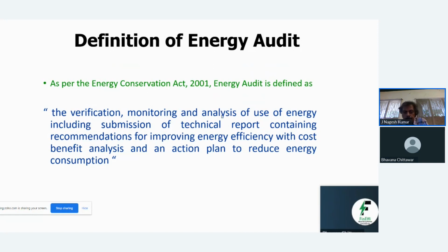If there is a compressor, where do we stop the analysis? We measure the electrical power input to the compressors as part of the energy audit. Diligently, we measure the power using a power analyzer. Today it's becoming a fashion to do the FAD test. I'm not really sure how helpful it is, but FAD tests are being conducted in all audits, also demanded by some clients. And the leak test, of course, is also carried out. So is that all that's required for a compressor system audit?